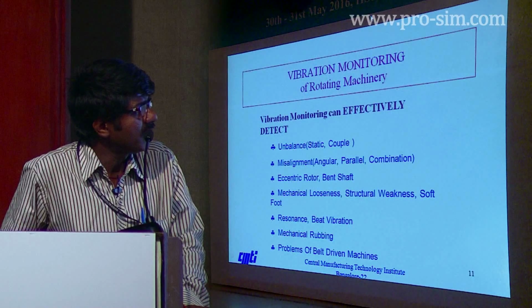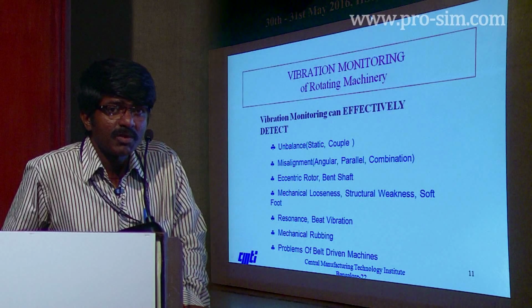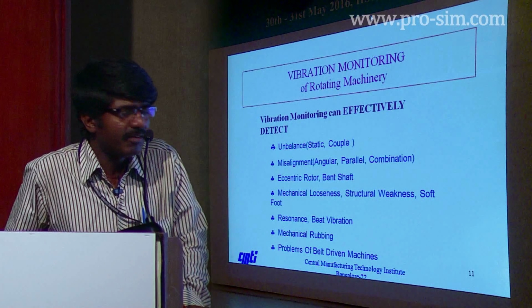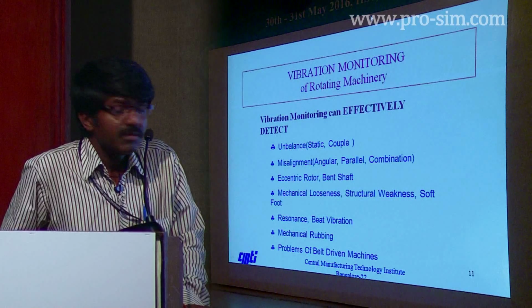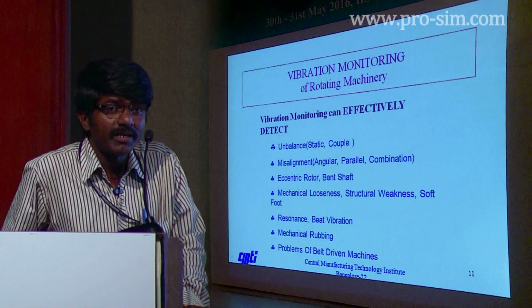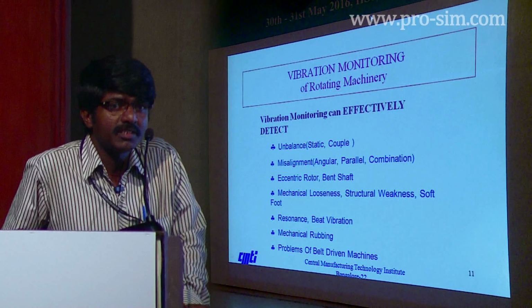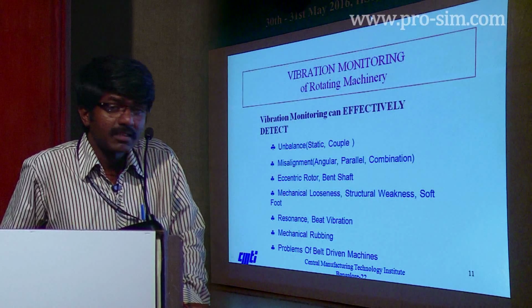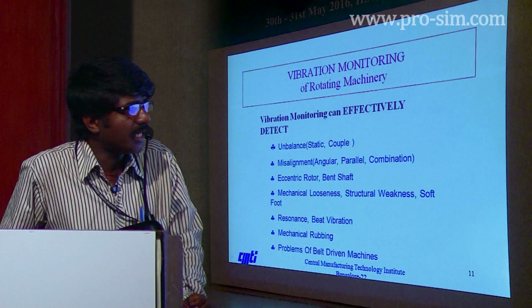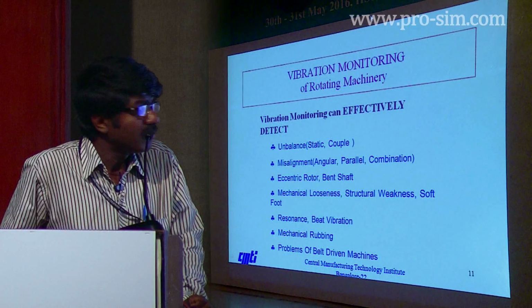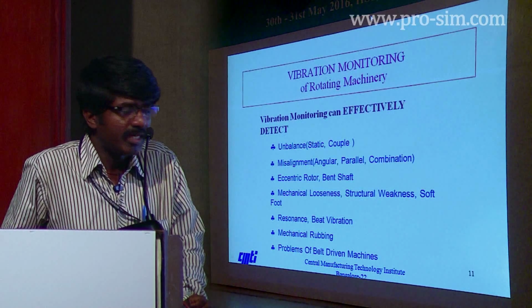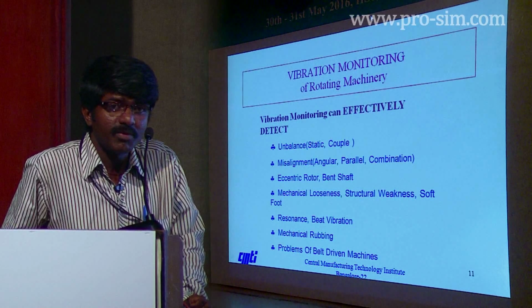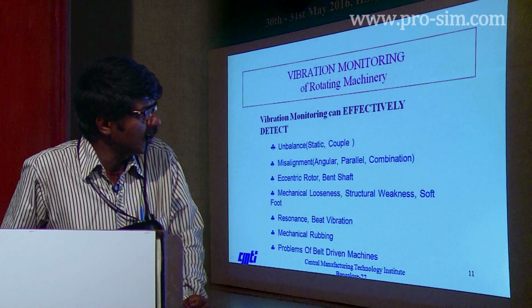Now we are coming to vibration monitoring. By using vibration monitoring, what are all the faults we can identify? We can identify unbalance. In unbalance itself, there are various types: static unbalance, couple, and dynamic unbalance. Then misalignment between the two mating parts, which may be angular, parallel, or a combination of these two.